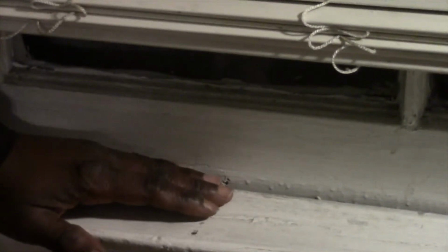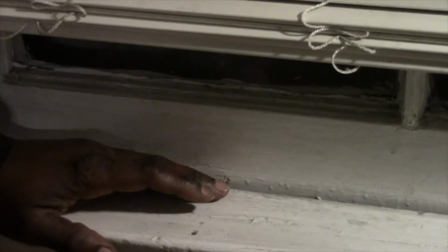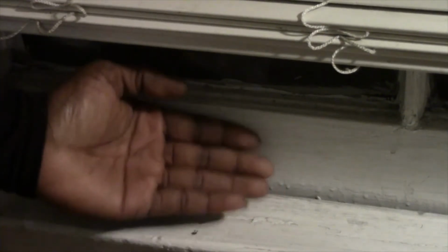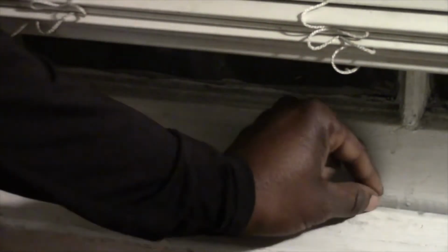So this space, it's a fairly good space right here. Like, that's significant. You can see my finger being able to pinch in there, and I can actually feel the cold air coming in, right? So that's real cold air infiltrating, and therefore you would expect this room to definitely be a few degrees off where it should be, just because you have that much cold air coming in. I can feel it even without a wet hand test. That gap is fairly substantial, right? And the window's down as far as it pretty much goes.